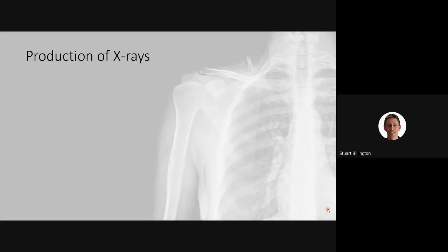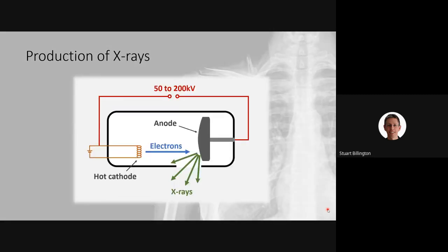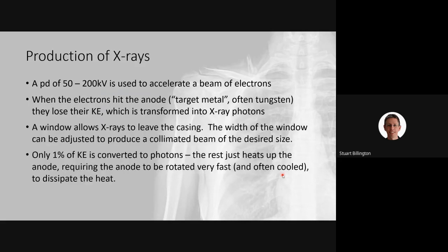So it's a spinning disk, actually, mounted on an axis here. So it rotates about this axis, round and round and round it goes. And what that means is that the part that's being heated up keeps changing. Now, the disk is spun pretty fast, actually, because the tungsten would melt fairly quickly if left in one place. So we spin it fairly quickly.